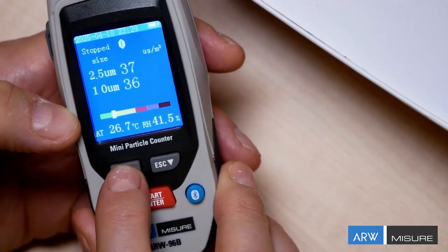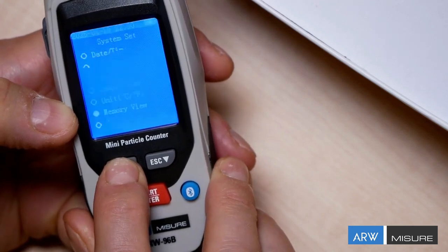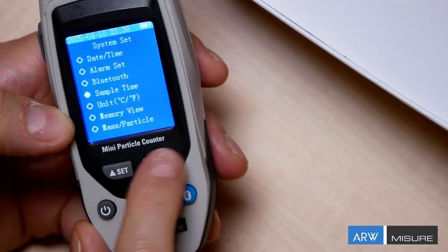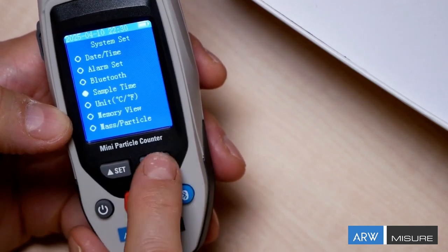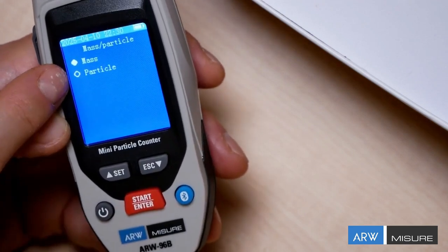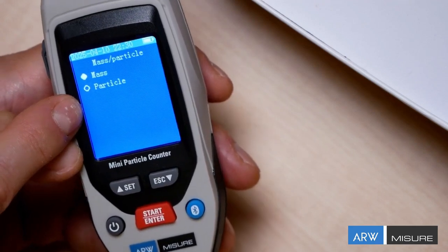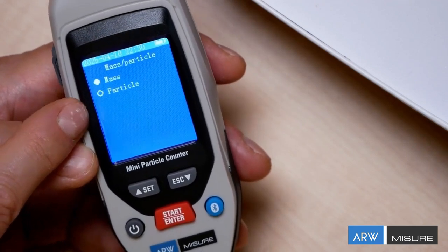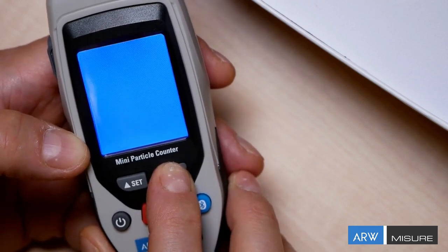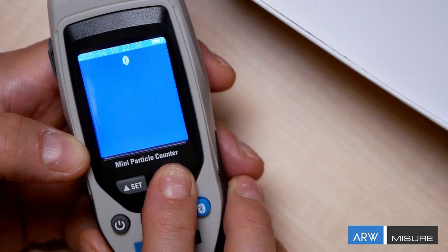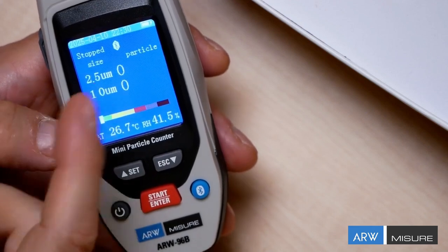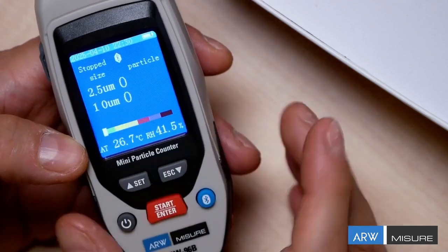One additional and noteworthy feature that we should definitely mention is the existence of a comprehensive internal settings menu that provides us with the capability to configure and adjust highly significant parameters, including the display. And not only that, beyond the total measurement of the mass, we can also measure and count the individual particles. So we can characterize the information on the display not just by mass, but by the specific particle count. It will function like a meter counter, a particle counter.